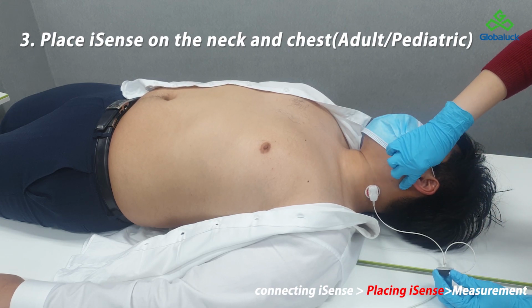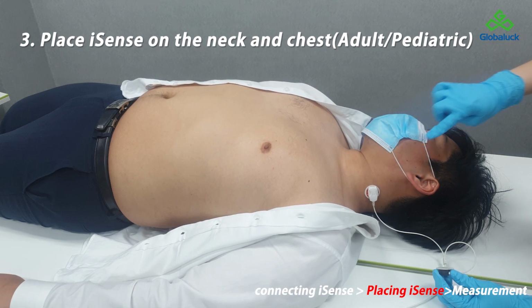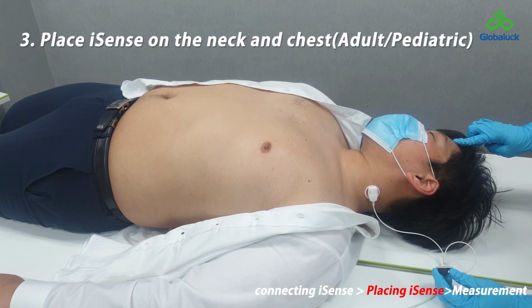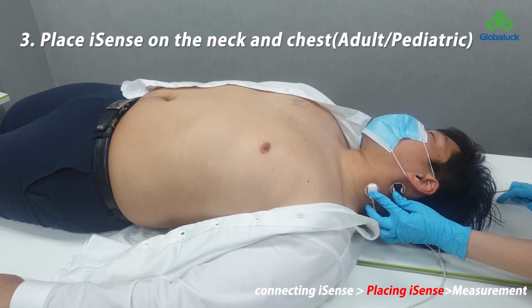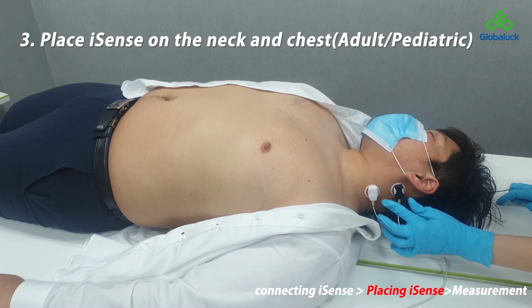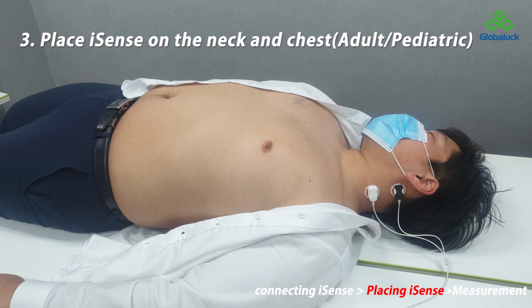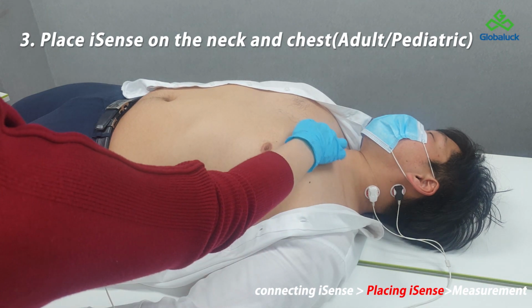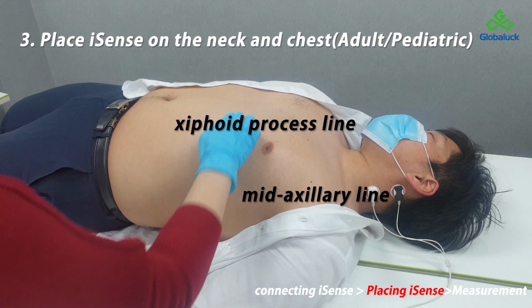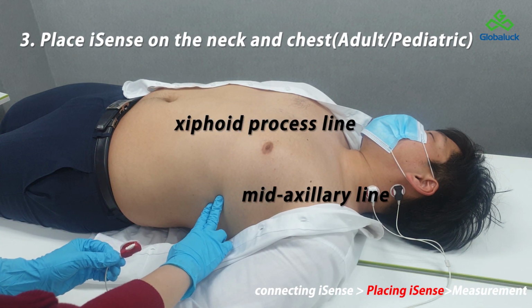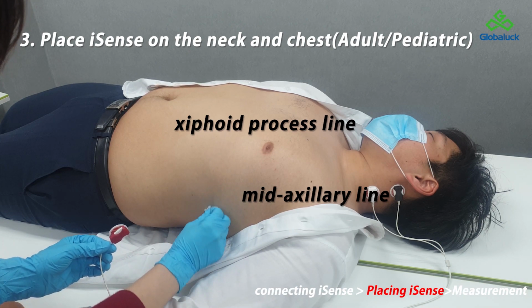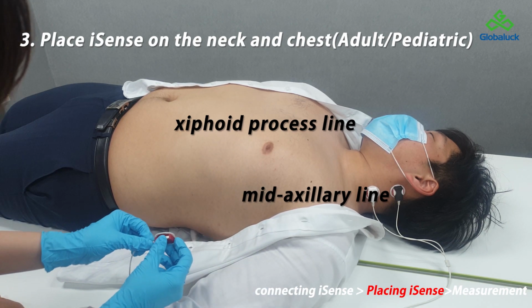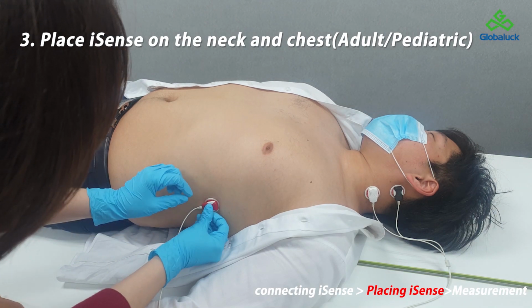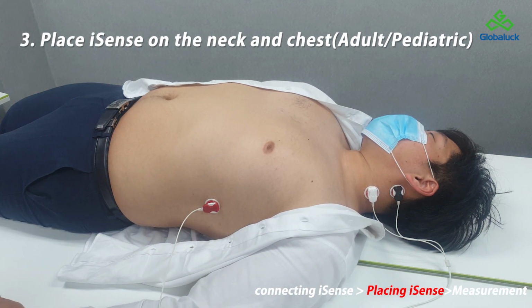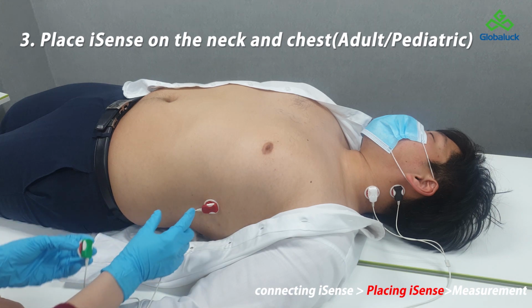The best way to place A and B is that the sensor B is attached at the left base of the neck and then the sensor A is attached about 5 centimeters above the sensor B. If you cannot attach the sensors A and B on the neck, you could alternatively attach the sensor A at the forehead or the temples. The sensor C is placed on the mid-axillary line at the xiphoid process level. The sensor D is placed about 5 to 15 centimeters below the sensor C.